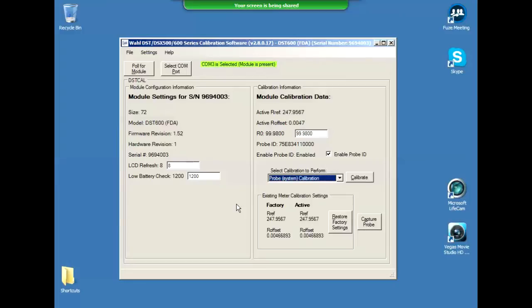Change the probe and hit capture probe. These are more for people doing electronic calibration. If you're doing that ohm meter calibration there, then the only option for the people using this program is to save these active defaults. And if for some reason they do something wrong, they can always restore to the factory settings. But all that restoration does is, that won't affect probe ID, that won't affect R0, and it won't affect these. It really is the calibration settings for the electronics of the instrument.